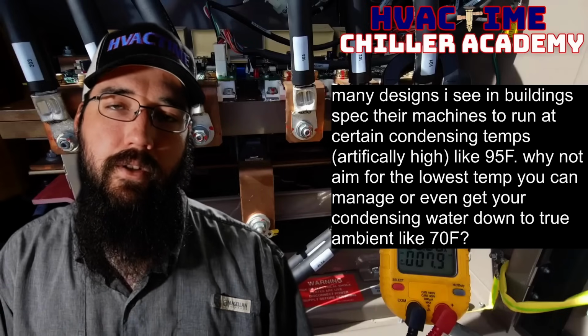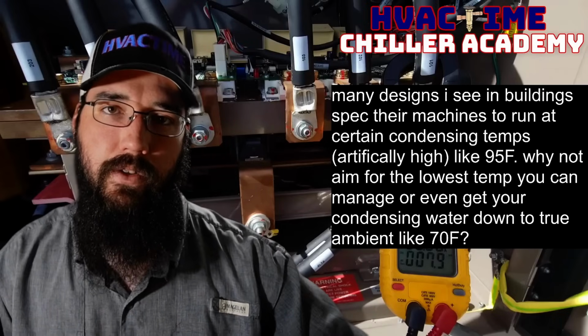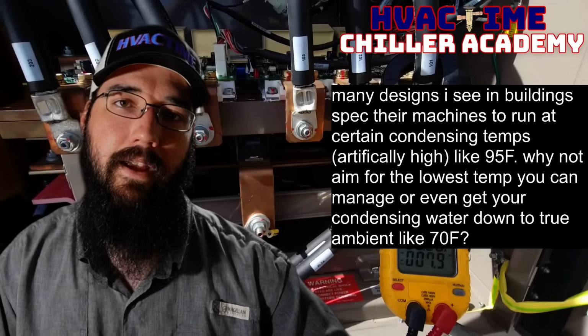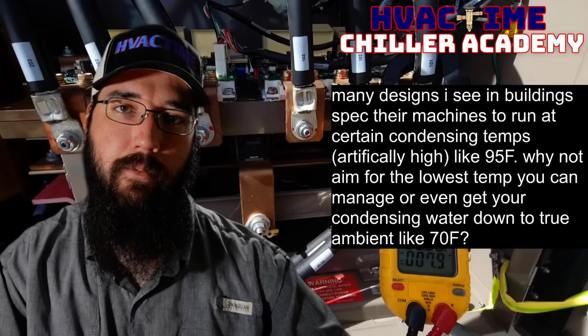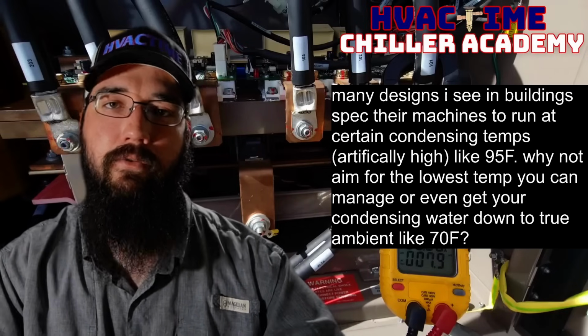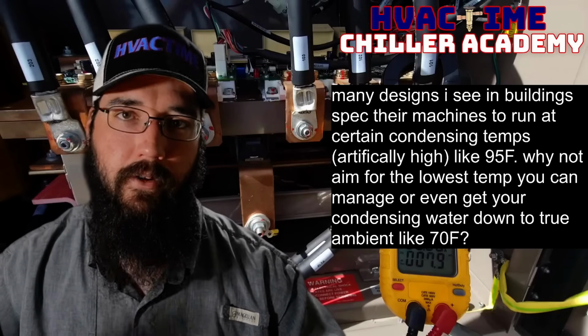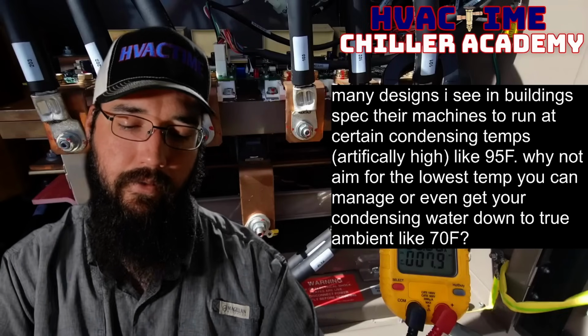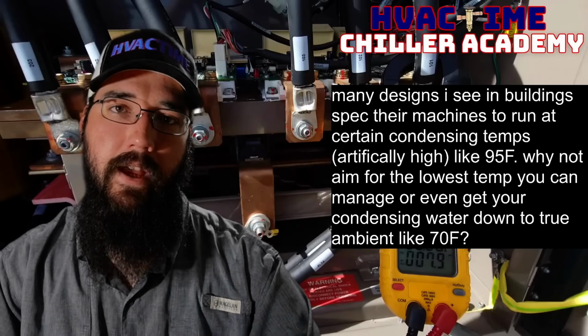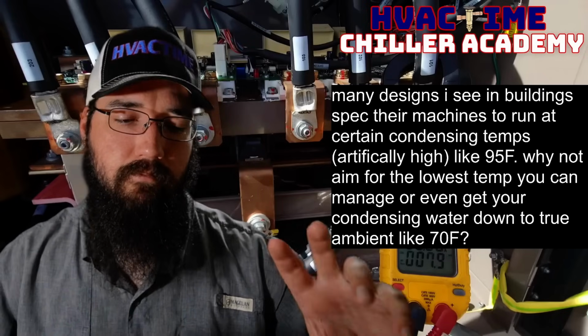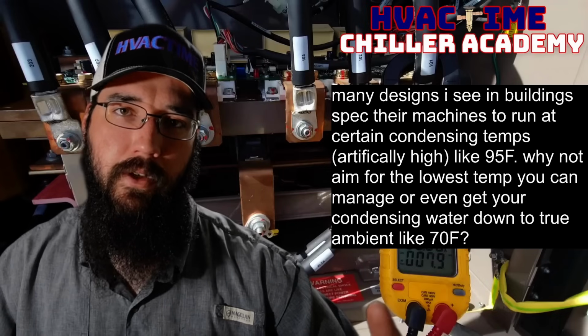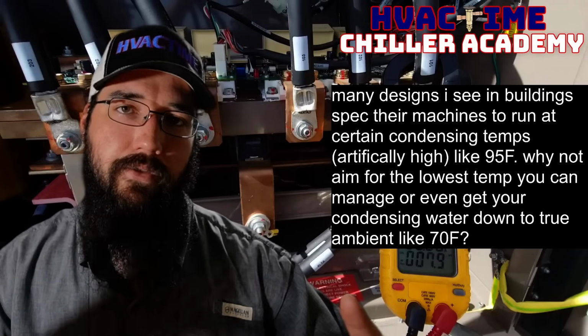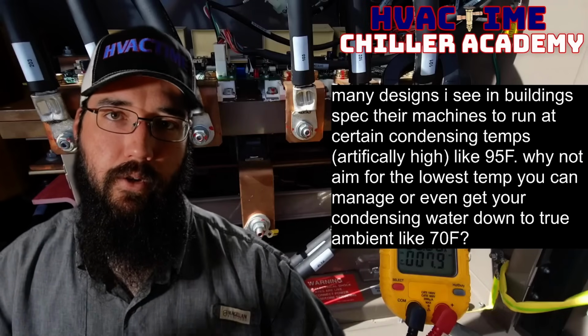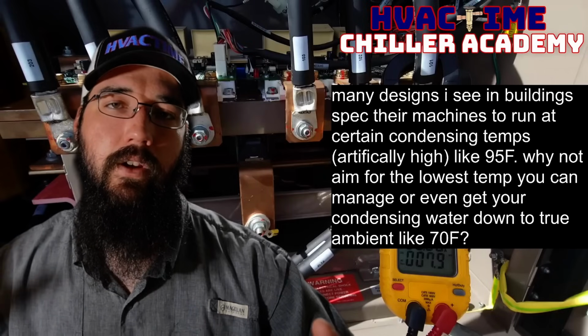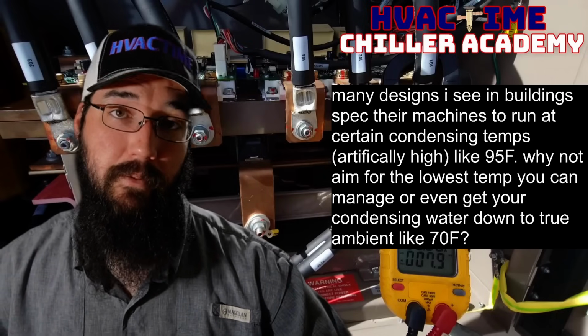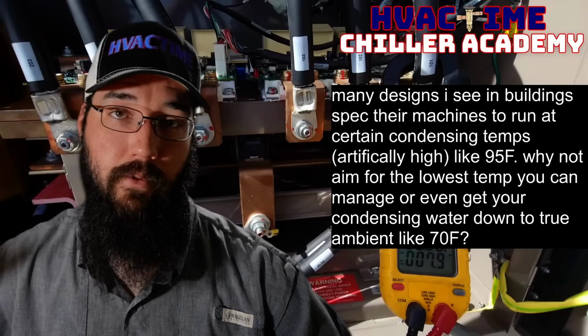So what you'll end up having is your control system can calculate wet bulb by taking the ambient outdoor temperature and the humidity, and converting that into a wet bulb temperature via psychrometrics. Okay, very basic stuff. And then we can plug that in to control the condenser water set point. So essentially it is wet bulb temperature plus 5 degrees, with a 5-degree approach, let's say, equals your condenser water set point. And let that be a variable set point.